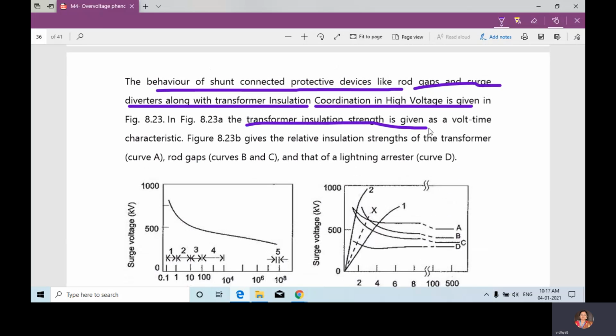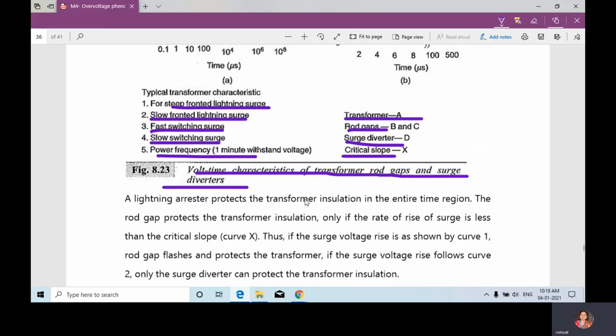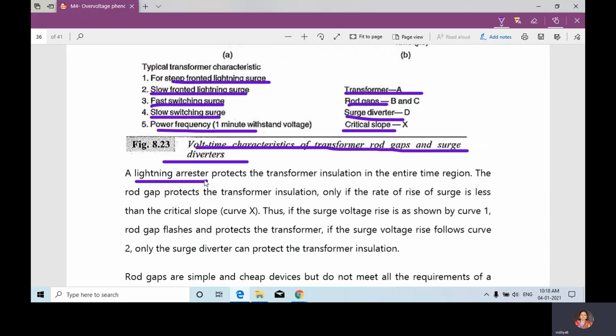The transformer insulation strength is given as volt-time characteristics. The relative insulation strength of the transformer is curve A, the rod gap curves B and C, and the lightning arrestor, that is curve D. What does the lightning arrestor do? The lightning arrestor will protect the transformer insulation in the entire time region. The rod gap, what does the rod gap protect? The rod gap protects the transformer insulation only if the rate of rise of surge is less than the critical slope. Okay.